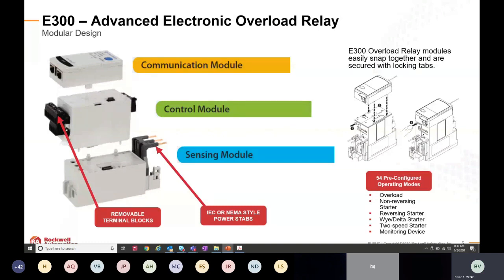There are 54 pre-configured operating modes. So if you know your application will use, say, a 2-speed starter, a non-reversing starter, or a reversing starter type application—just naming a few examples, there are many more—you can put the E300 into one of those modes, and it will pre-configure itself in the most basic and common configuration, so you don't have to program each individual parameter manually. It's kind of like express programming, if you're familiar with programming a frequency drive.